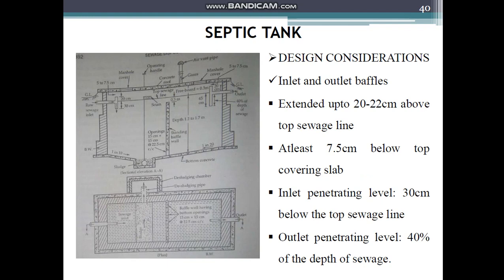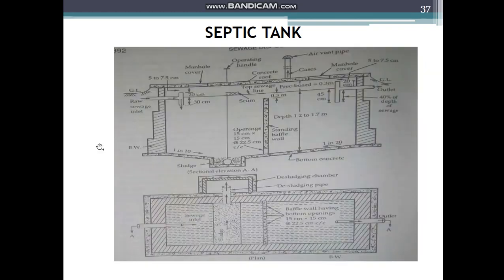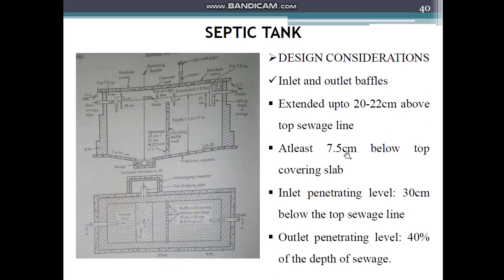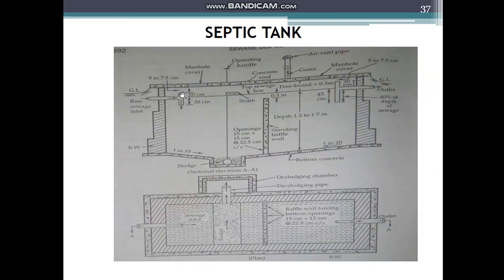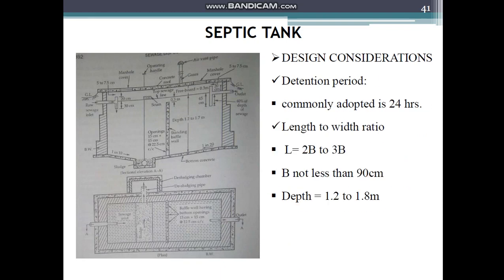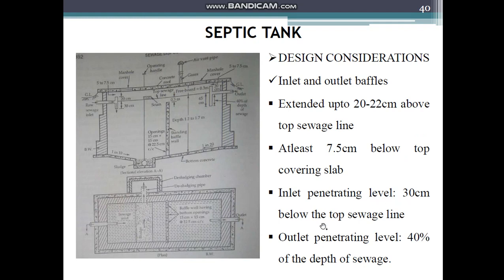The inlet and outlet pipes extend 20 to 22 centimeters above the top sewage line, and at least 5 to 7.5 centimeters below the top covering slab. The inlet penetrating level is 30 centimeters below the top sewage line, and the outlet penetrating level is 40% of the depth of sewage.